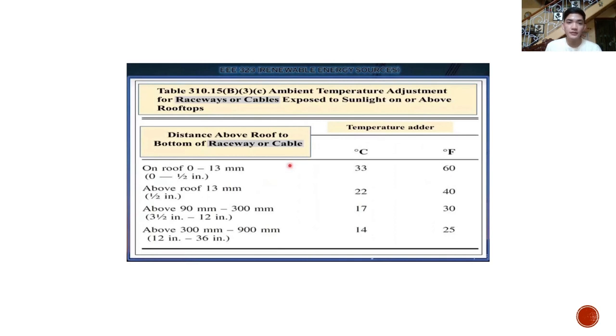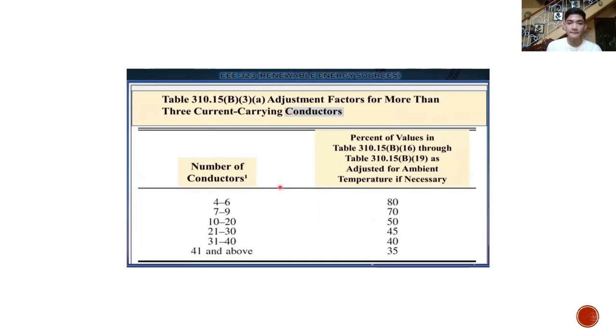Ambient temperature adjustment for raceways or cables exposed to sunlight on or above rooftops. Distance above roof to bottom of raceways or cable: on roof, 0 to 13 millimeters is 33 degrees Celsius or 60 degrees Fahrenheit. Above roof 13 millimeter, 22 degrees Celsius or 40 degrees Fahrenheit. Kapag naman above 90 millimeter to 300 millimeter, 17 degrees Celsius or 30 degrees Fahrenheit. Kapag naman above 300 millimeter to 900 millimeter, 14 degrees Celsius or 25 degrees Fahrenheit. Next is adjustment factors for more than 3 current carrying conductors.